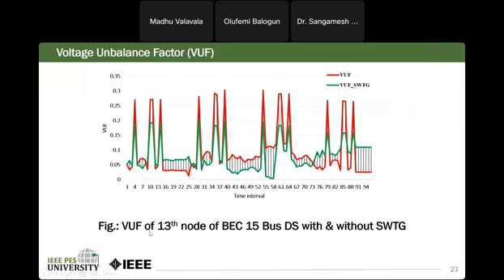Similarly, the voltage unbalance factor also improved as per the standards. If the voltage unbalance factor is less than 2%, it is not a concern. That's why the SWTG is connected to the 13th bus. Based upon this green color symbol, the voltage unbalance factor is slightly reduced.